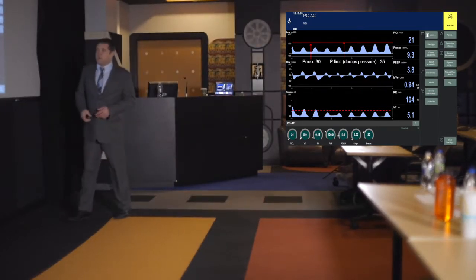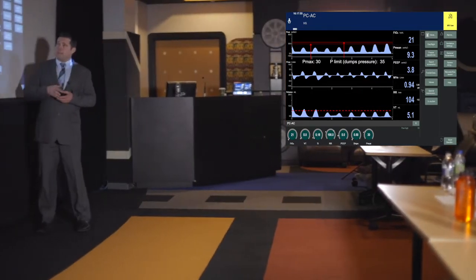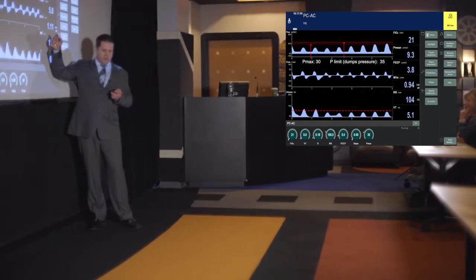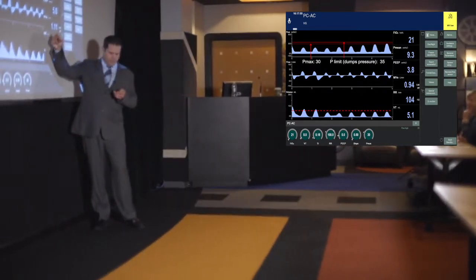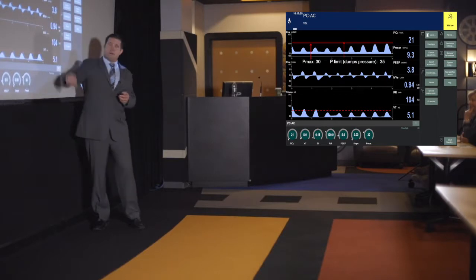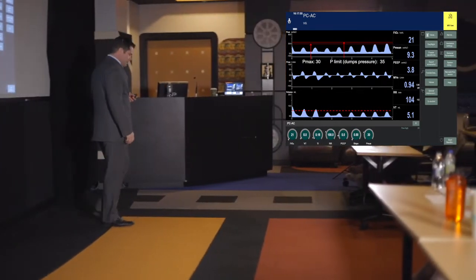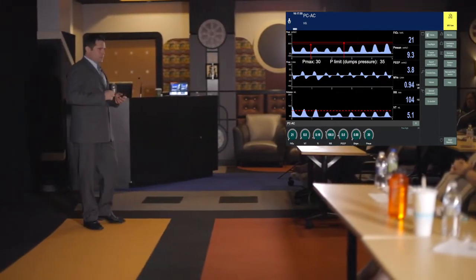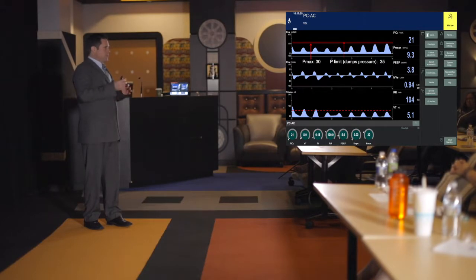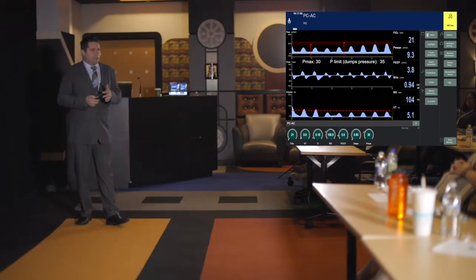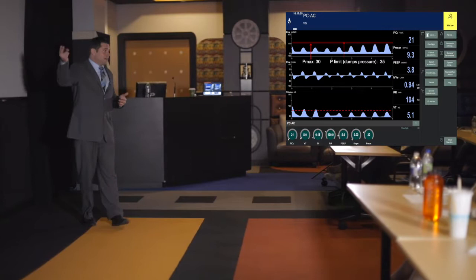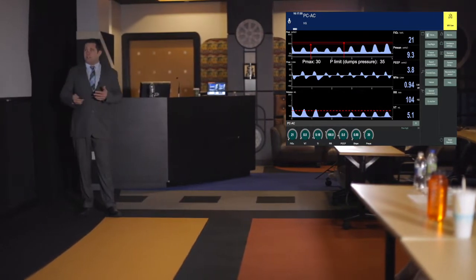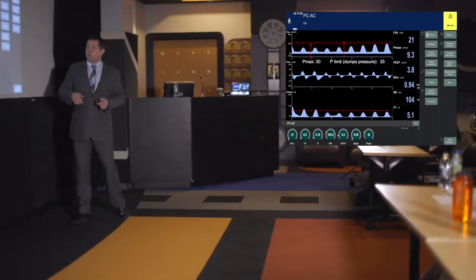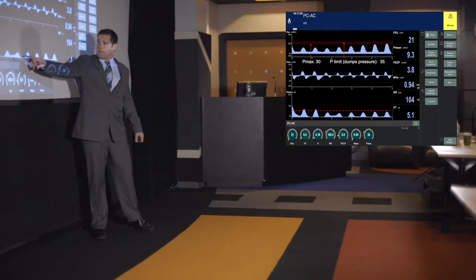And so in the ventilator we use, we set the Pmax setting, and then the ventilator will dump once it's 5 above that Pmax setting. And we've really gotten pretty good at trying to set that about maybe 10 to 15 above what they're currently ventilating at. But then if they have a leak, we need to go much higher. If they have BPD, we need to go much higher. But anyway, the ventilator will dump the breath as it has right here.